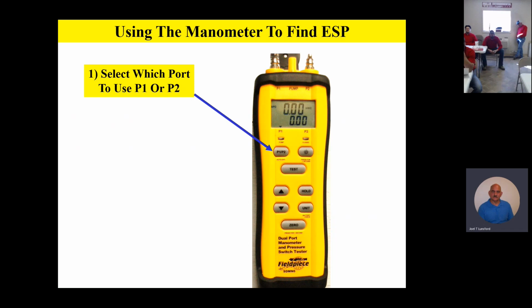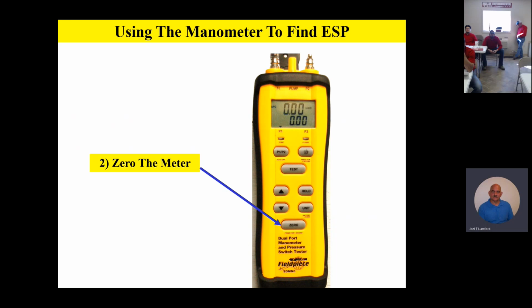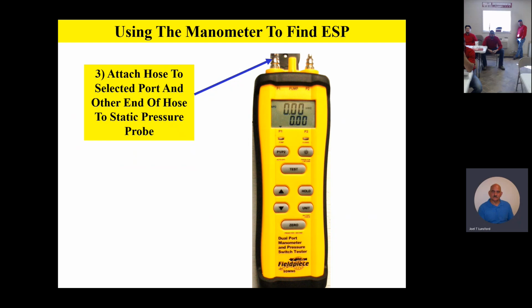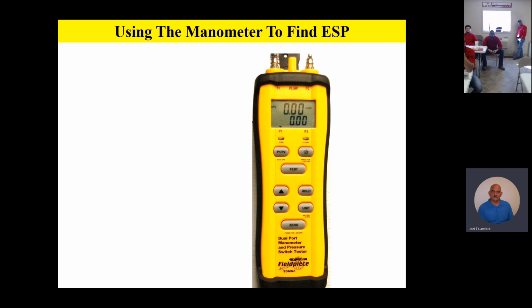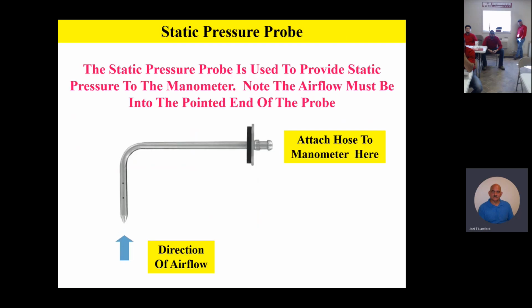So select which port you're going to use, P1 or P2. Then zero the meter, and make sure the meter is zeroed. Then you're going to attach your hose to whatever port you're using, and the other end of your hose to your static pressure probe. Now let's take a look at that. This is what a static pressure probe looks like. It's used to provide the static pressure to the manometer.